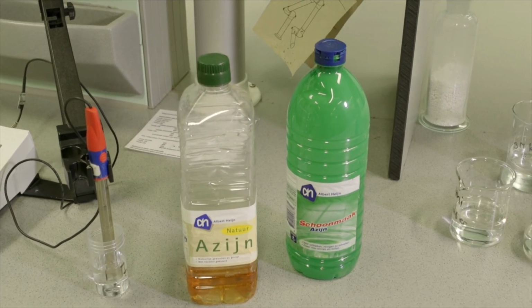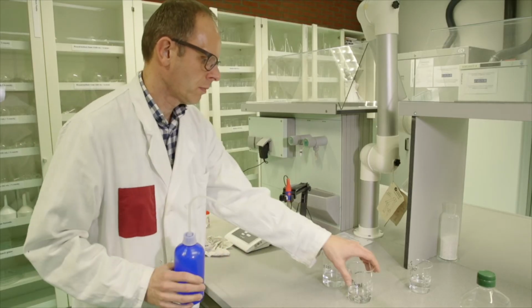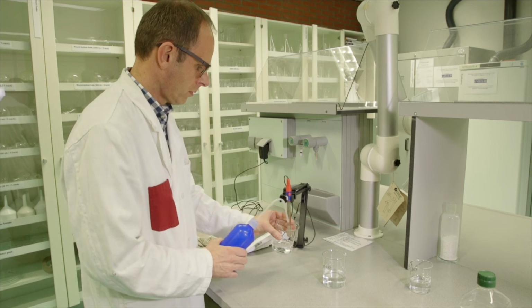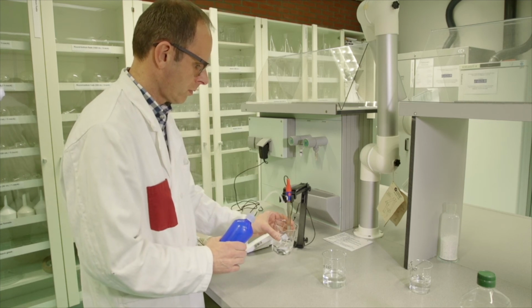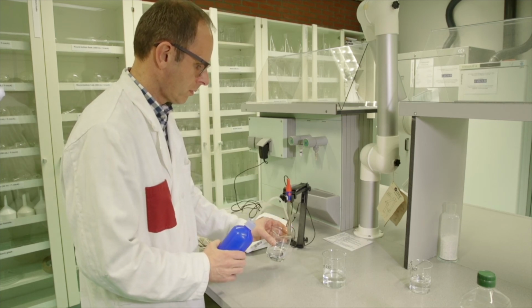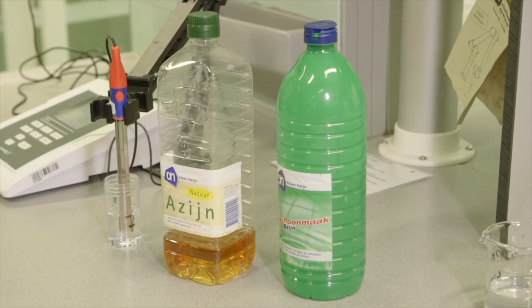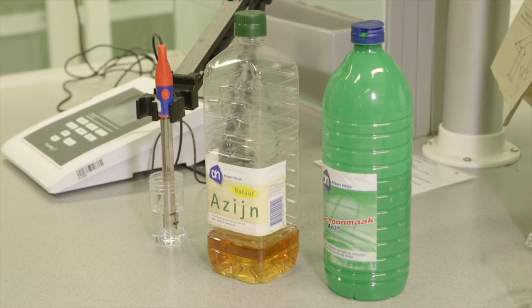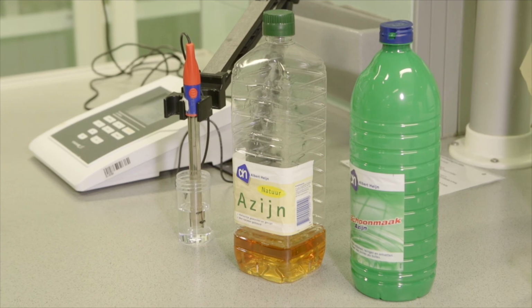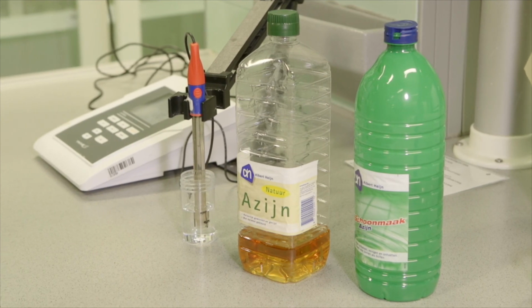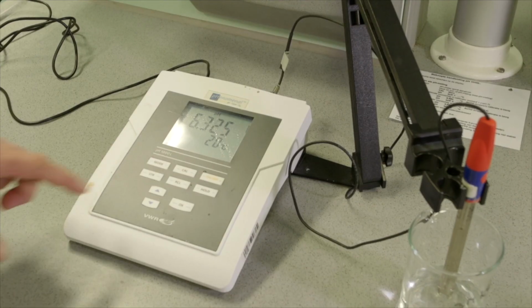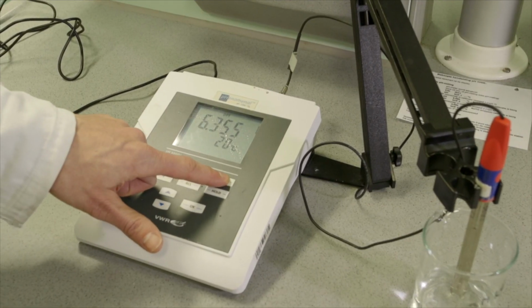Remember to rinse off and dry the electrode before putting it into the liquid to be measured. In addition, electrodes are easily broken, so pay attention when using a stirring rod as it can easily break the electrode. Never use your electrode as a stirring rod. When you are finished with measuring, the device must be switched off by pressing the on-off button and then pulling the plug out. The pH electrodes are always kept in 3 molar potassium chloride solution.